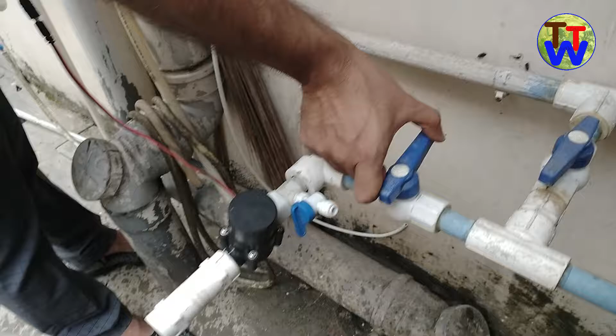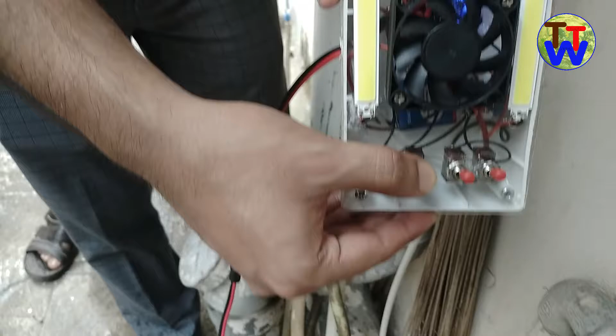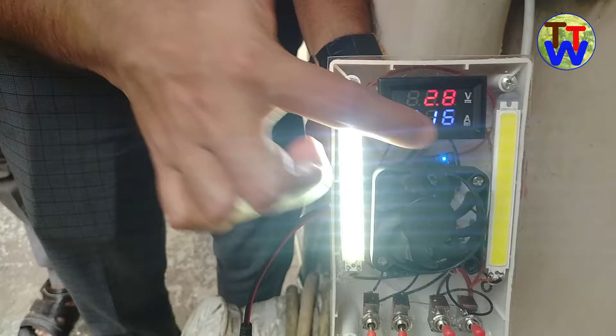So we'll gradually turn on the water supply. We have to keep in mind that first, when we are turning on the Pico-hydro turbine, no load should be turned on. Load should be turned off. So the Pico-hydro turbine should be turned on at no load condition. Then gradually we are connecting the loads, switching on the loads, first at no load condition, then you will gradually switch on the loads. So then the turbine won't overspeed or get damaged, or pitting will not take place in the turbine.